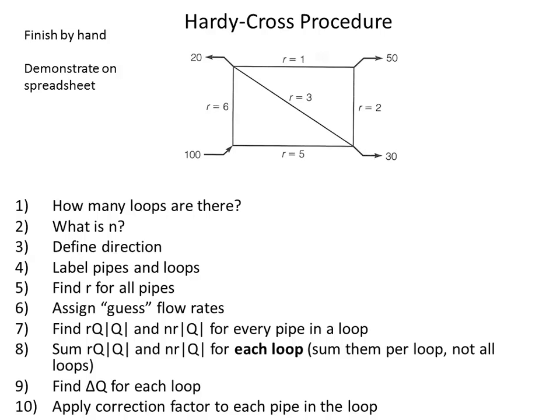Chase, what about pipe 1-3? What value should I put in for pipe 1-3? Negative 1.3. Good, you caught yourself there. So 1.343, this is the most recent estimate I have of the flow rate, but then I'm changing the sign. Because when I was talking about the flow rate here, that was from within the context of loop 2. Now I'm back in loop 1.